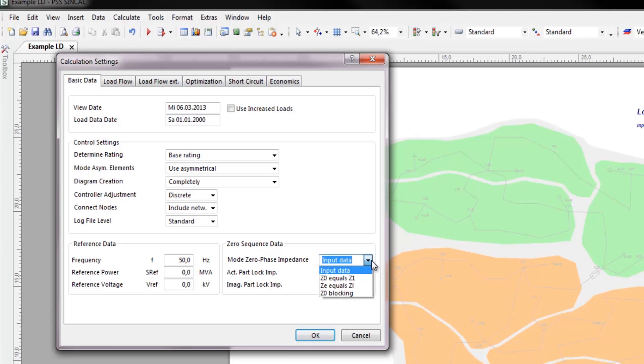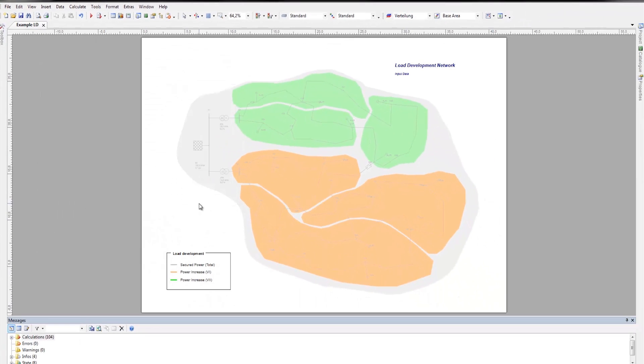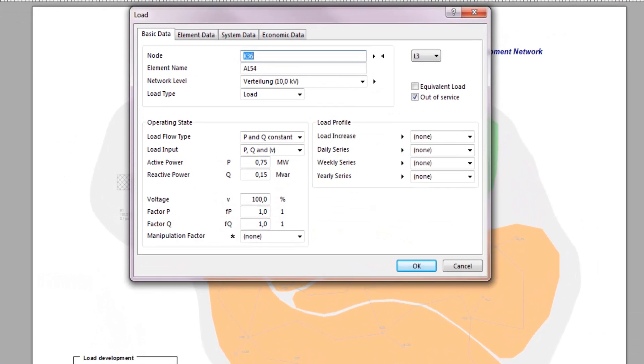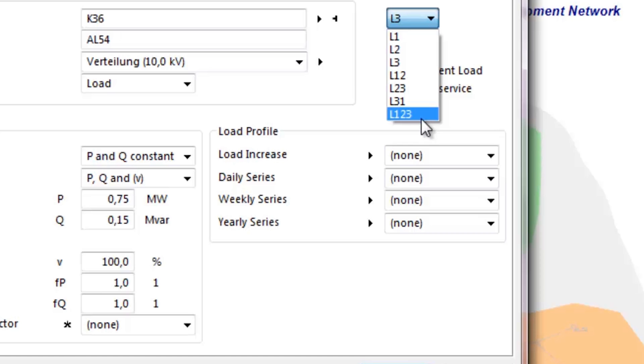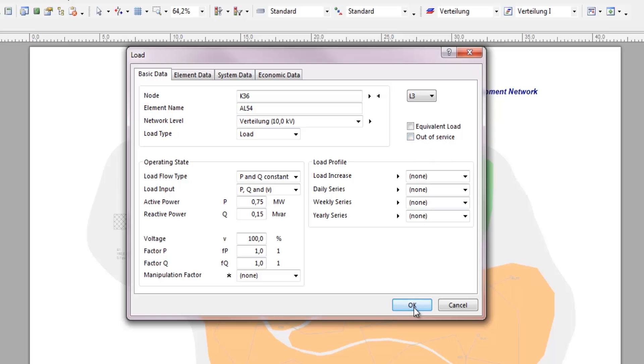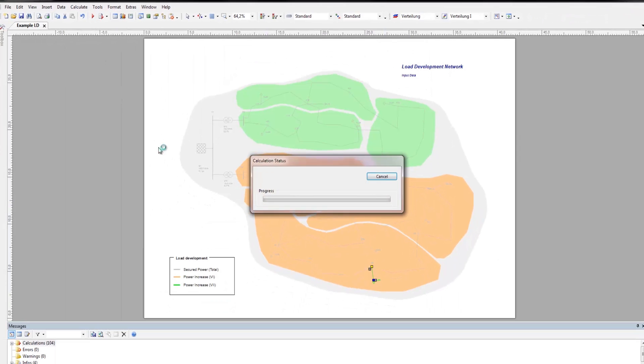Mode Zero Phase Impedance is used to set impedance so that network elements without zero-phase sequence data will be considered in calculations. PSS SINCAL displays network data for unbalanced network elements in the same data screen form as symmetrical elements — the only difference is their connection type. To demonstrate this, consider adding a single-phase node. On creation of new network elements, the default setting is a symmetrical terminal with all three phases L1, L2, L3. In the network data of the load, it is possible to define the load as single-phase. Switch on the single-phase load and repeat the simulation with standard load flow — it is clear to see that the results are now for asymmetrical load flow.